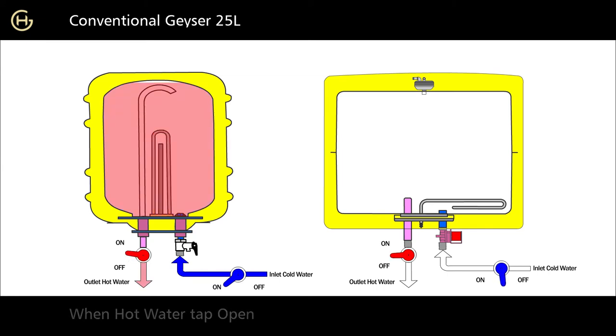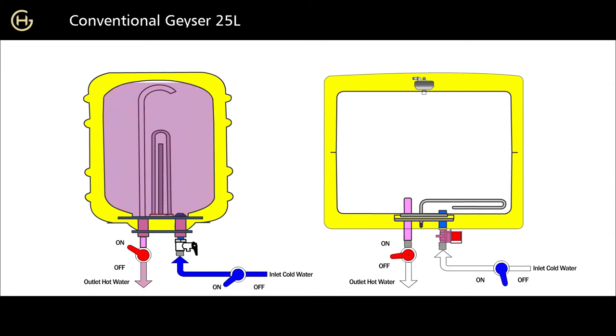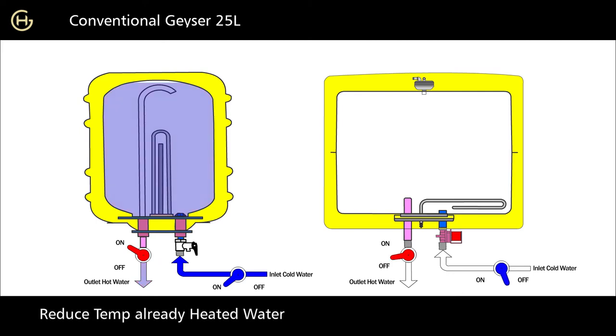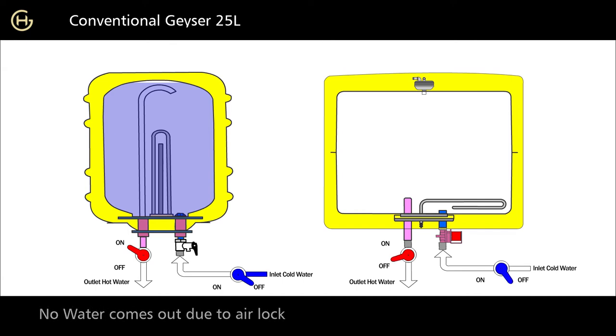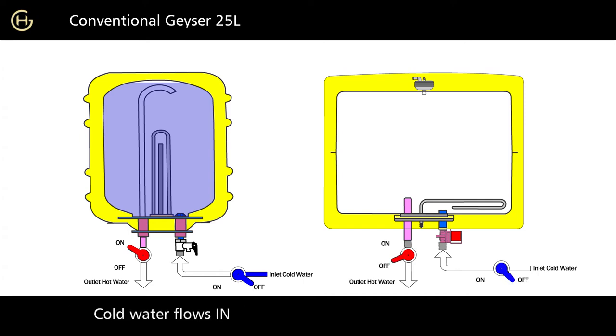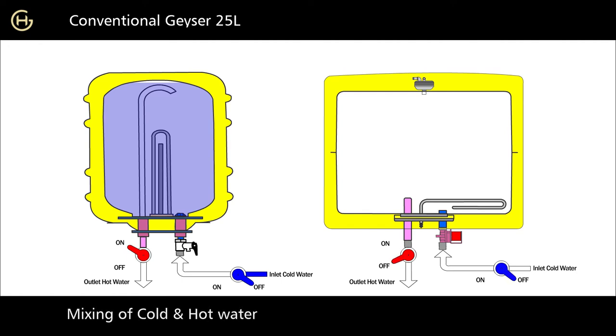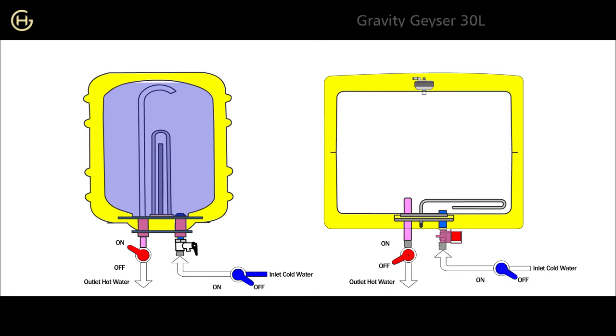When the hot water tap opens, cold water flows in and pushes out the hot water. In this process, cold water mixes with hot water and reduces the temperature of already heated water, which cannot be avoided. If the inlet cold water tap is closed and the outlet hot water tap is open, no water comes out due to air lock. So in the displacement principle, hot water comes out only when cold water flows in, and there is always mixing of cold and hot water, resulting in a loss of energy.